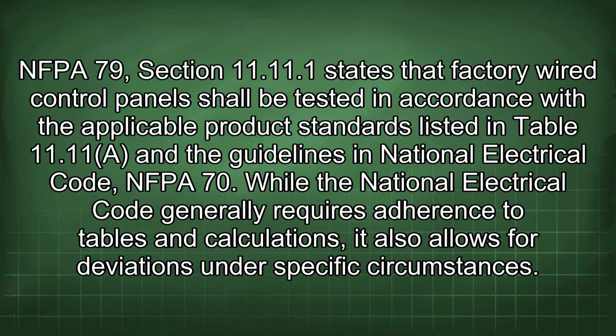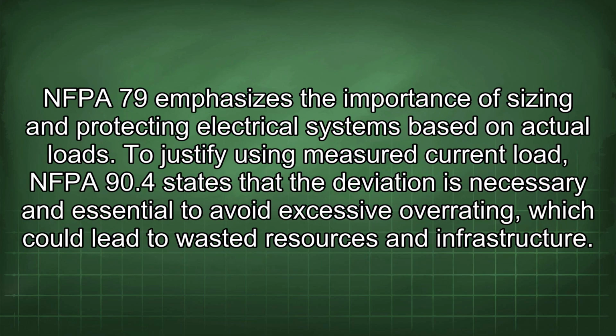While the National Electrical Code generally requires adherence to tables and calculations, it also allows for deviations under specific circumstances. NFPA 79 emphasizes the importance of sizing and protecting electrical systems based on actual loads. To justify using measured current load, NFPA 90.4 states that the deviation is necessary and essential to avoid excessive overrating, which could lead to wasted resources and infrastructure.